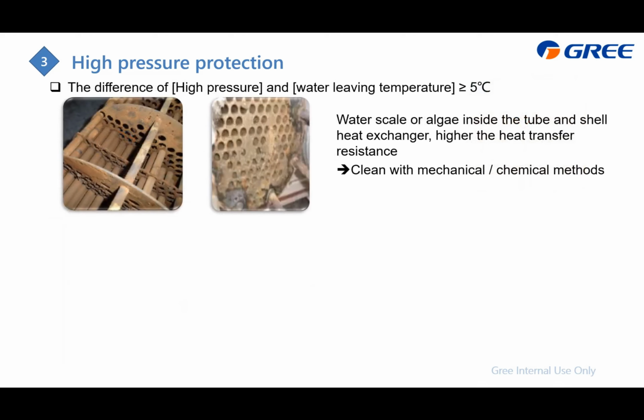If the system is in heating mode, you can also check the difference between the high pressure, which is the refrigerant saturated temperature, and the water leaving temperature. The difference of these two should be less than 5. If higher than 5, that indicates there is too much water scale or algae inside the tube and shell heat exchanger. This will raise the heat transfer resistance, which means we need a higher temperature of the refrigerant to deliver the heat to the water. And higher refrigerant temperature also means higher pressure. The countermeasure for this is just to clean it, just like these pictures, to clean the scale or the algae with mechanical or chemical methods.